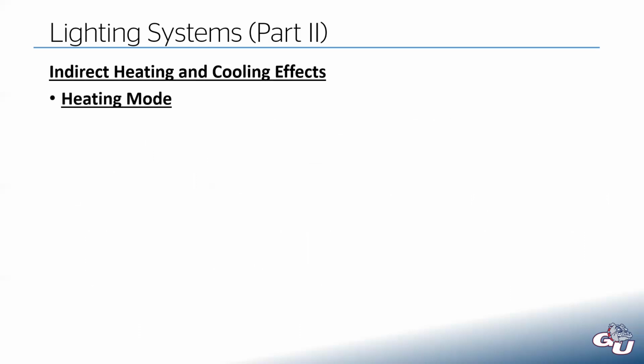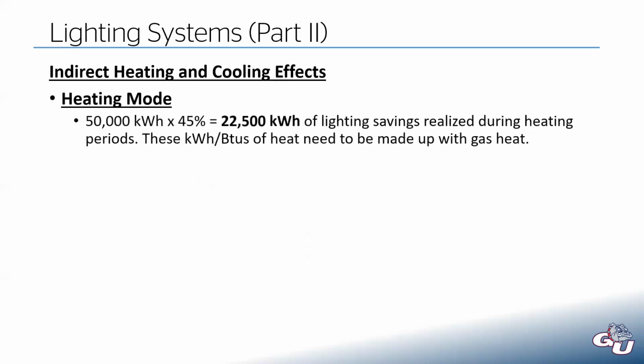Let's look at heating mode first. In heating mode, we said we are in heating mode about 45% of the time, which means of that 50,000 kilowatt hours that we are saving over the year, 22,500 of that are going to be seen during those heating periods, for the 4 months, 5 months out of the year. And so if we are saving those 22,500 kilowatt hours of energy, now our heating system has to make up that difference, because that was heat that was going into the space that's not anymore.